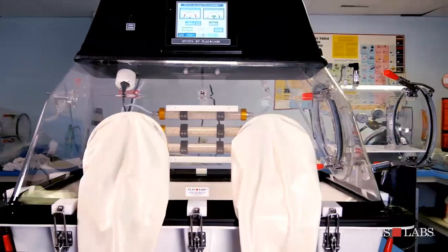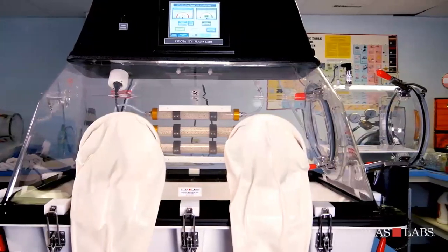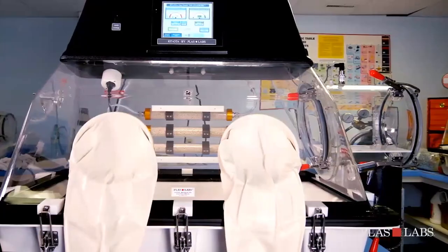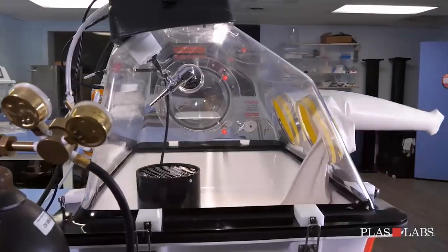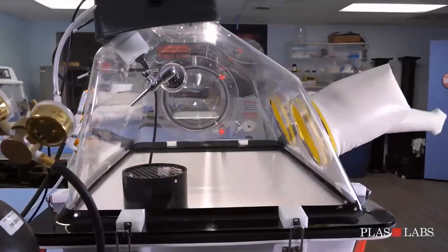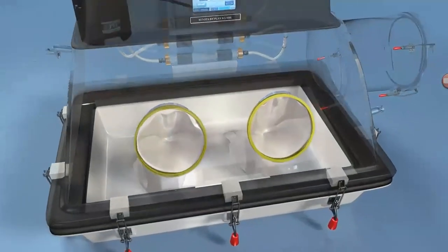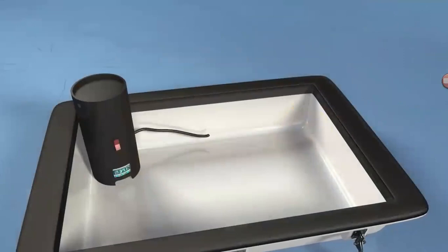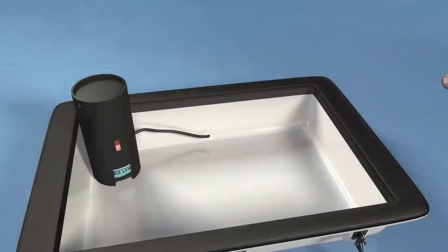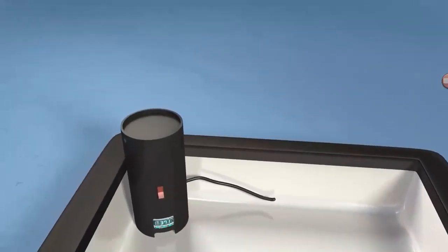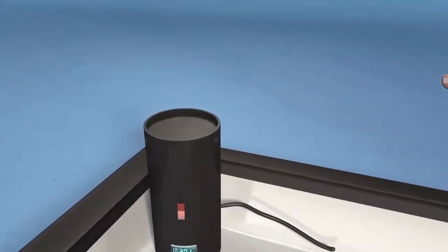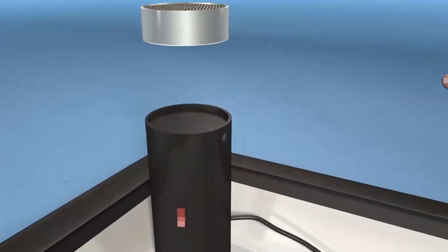A purging cycle consists of drawing a slight vacuum, -2 inches of water column, and then filling with a gas to a slight positive pressure, +3 inches water column. To operate, turn on the catalyst heater unit and place the thermocouple away from the heater. The heater temperature is factory set. Allow 5 to 10 minutes for the heater to reach its set point. Place the palladium canister on top of the heater.